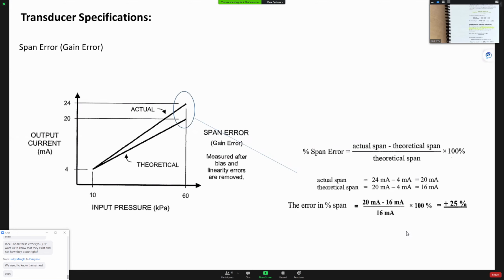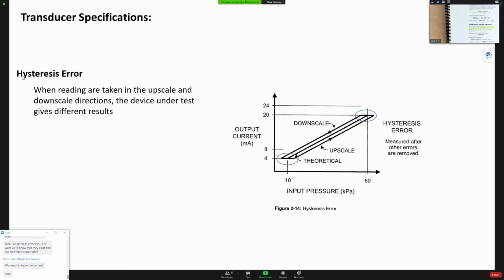Another one is called a hysteresis error, or the dead band. When you're using a transducer to measure something, measuring from the lower value to the higher value versus measuring from the higher value down to the lower value will actually give you different values.